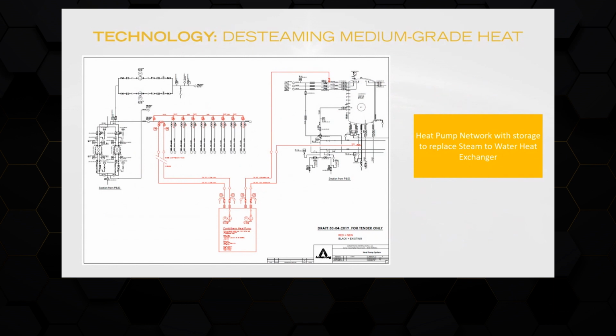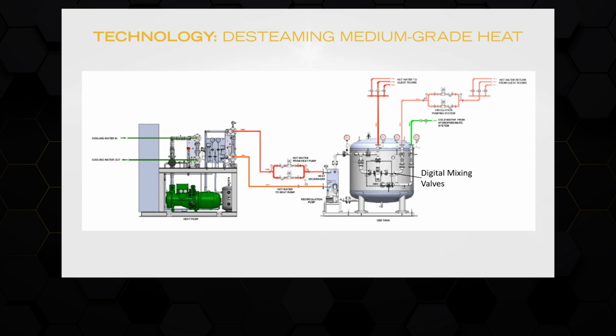A similar heat pump network was designed on cooling tower water, but considering the paucity of time, I will not be discussing that project. However, what I will develop upon is digital mixing valves that are installed in the hot water loop after the storage tank. A complex thermal demand of flow and temperature cannot be met by individual heat pumps. So to cater to those complexities, a mixing valve helps us deliver hot water at the precise temperature required by the process, while the heat pump can operate at its best COP delivering the temperature set point.